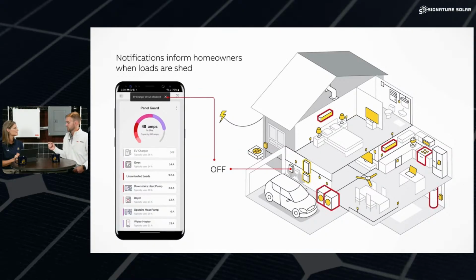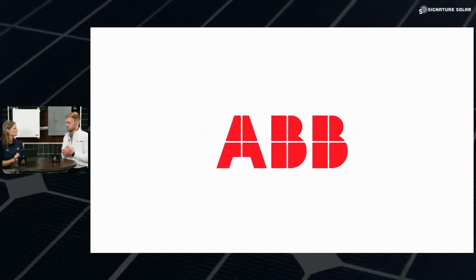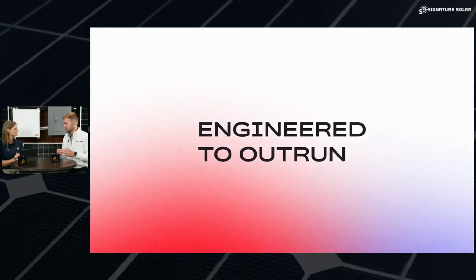Those relays are designed to connect to up to 12 circuits in a load center. That could be 12 single pole, 120 volt circuits, it could be 6 dual pole, 240 volt circuits, or any combination of those two.